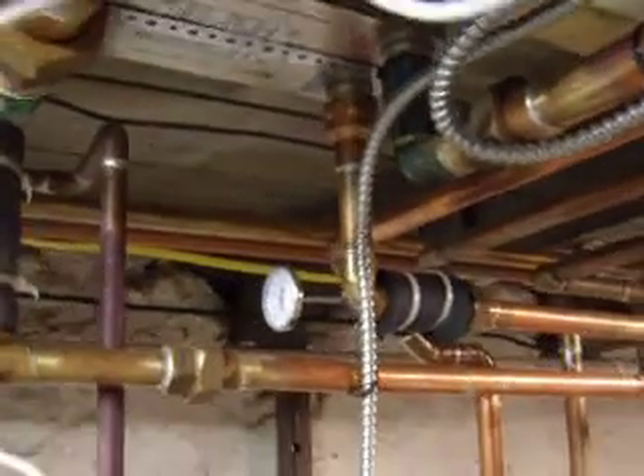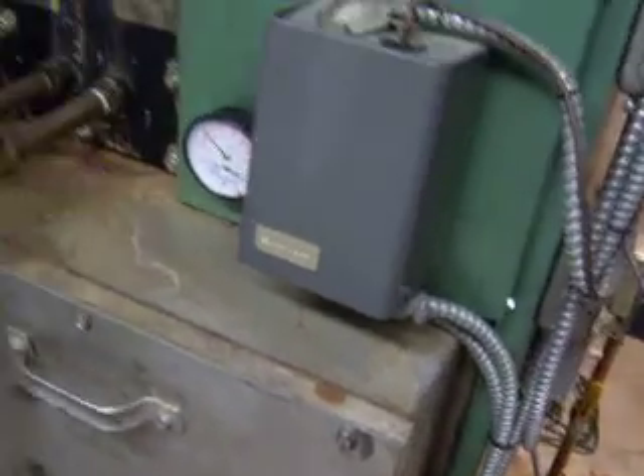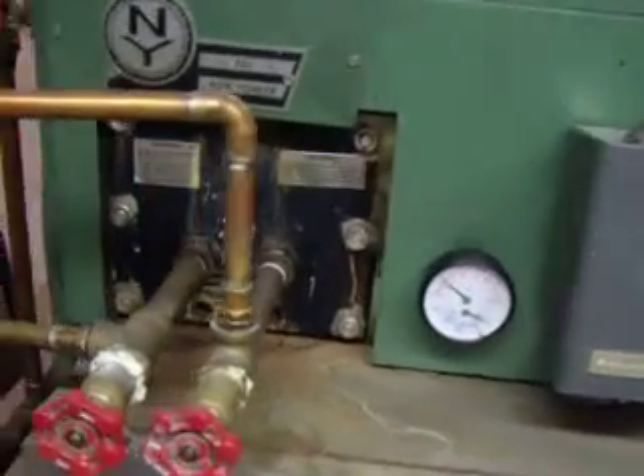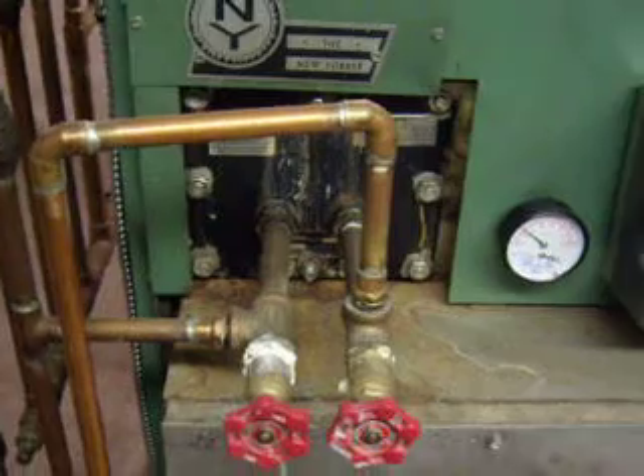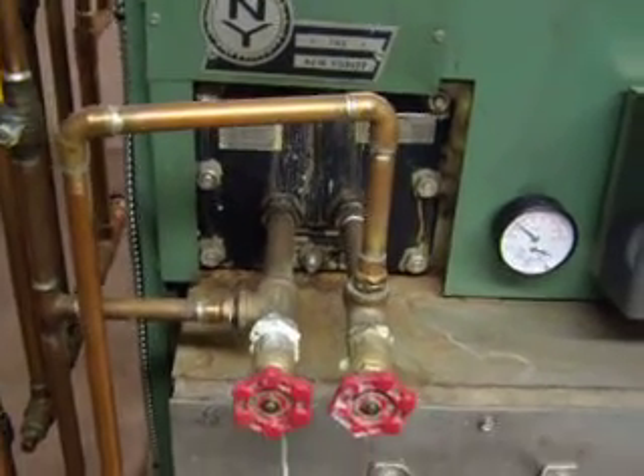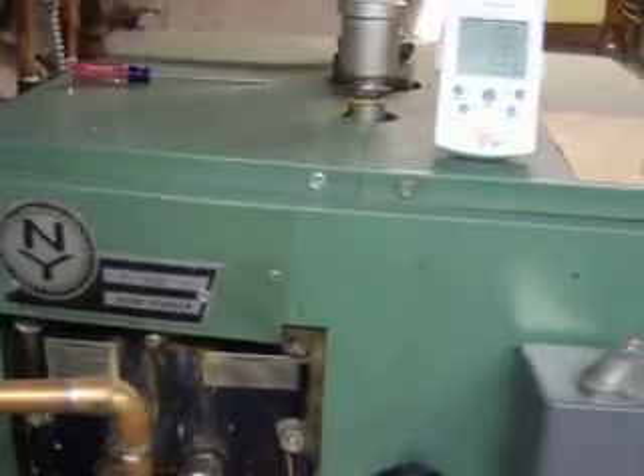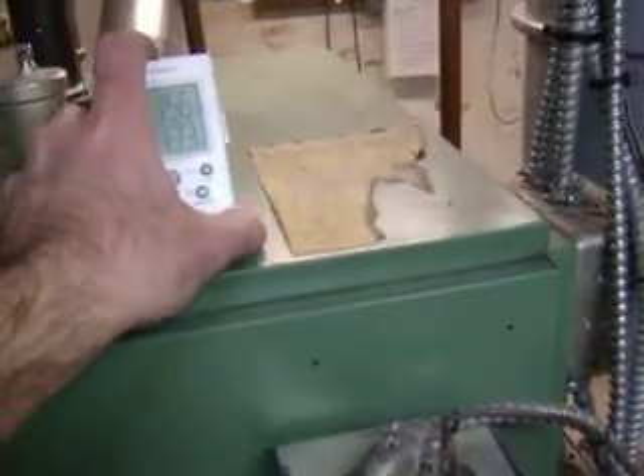That's a big plus. So again, the big reason I'm running the heat exchanger is just because I didn't want the glycol from the wood boiler mixing with the inside of the house boiler. If there were ever a leak in the domestic coil, you could get glycol contamination in your domestic water, and just to avoid that, I wanted to use the heat exchanger. So I might be losing a little bit of efficiency with the heat exchanger, but overall safety of the system works real well.